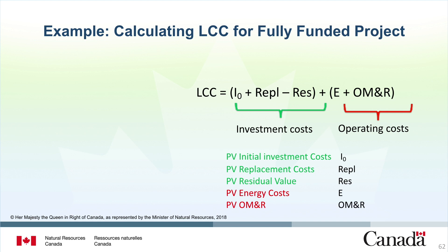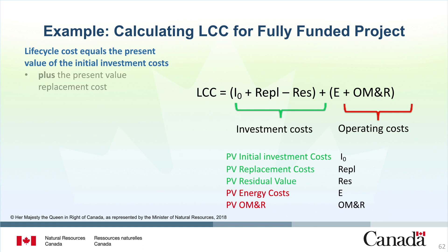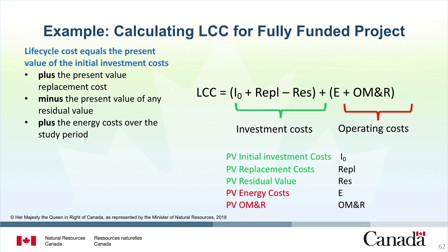Now let's list the data inputs for the alternative case. The alternative is to install a heat pump system to replace the old system. Because you are purchasing and installing the equipment, there will be an initial upfront cost of $2,841. There will be no replacement cost because the useful life of the equipment is 20 years and this is a 15-year study period. There will be some residual value because there are 5 years or 25% of useful life remaining at the end of the study period, which equals $710 of the initial cost. The electricity consumption will now be 16,290 kilowatt hours at 13.08 cents per kilowatt hour, the annual maintenance cost will be $450, and the compressor will require repair in year 8 at a cost of $1,200.